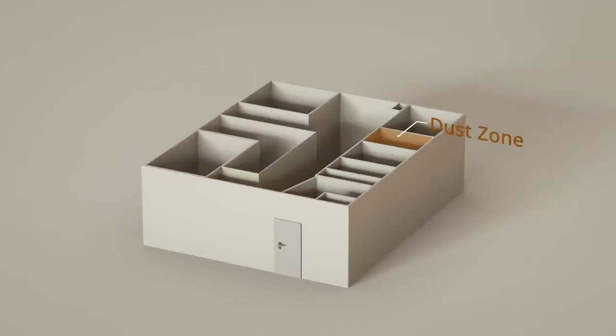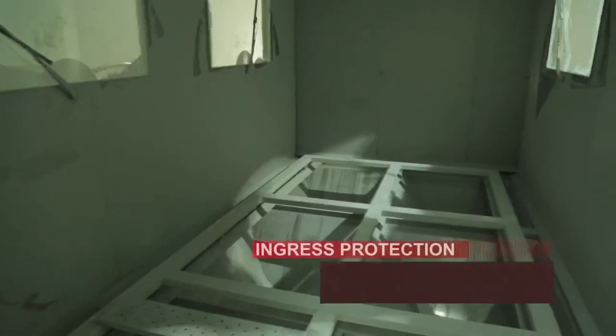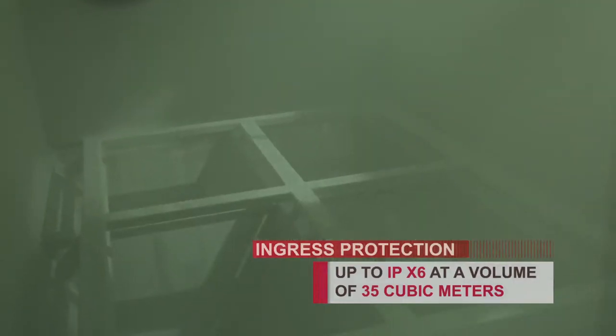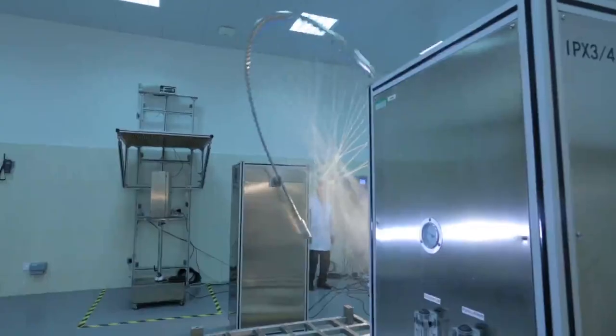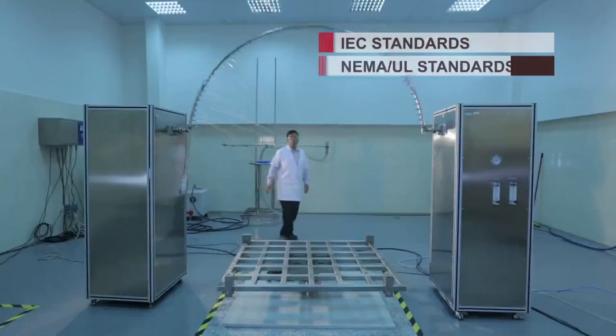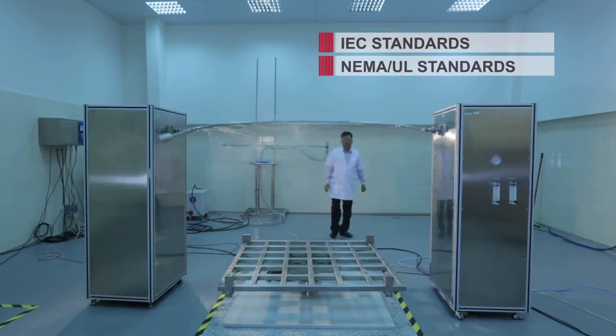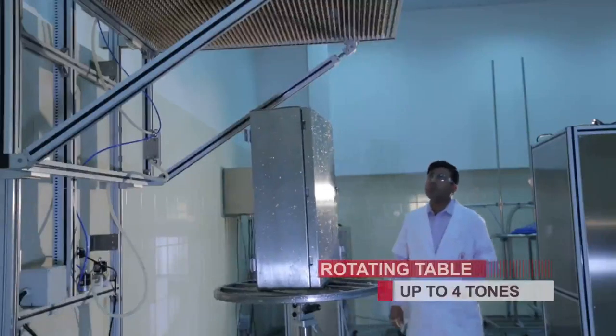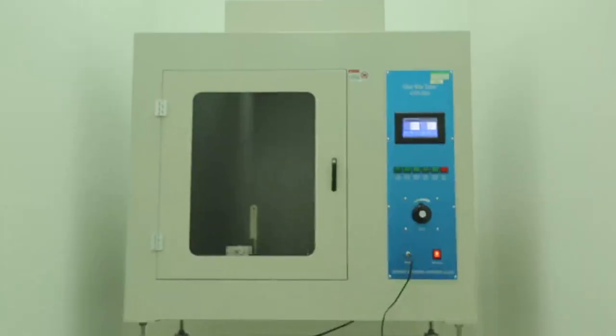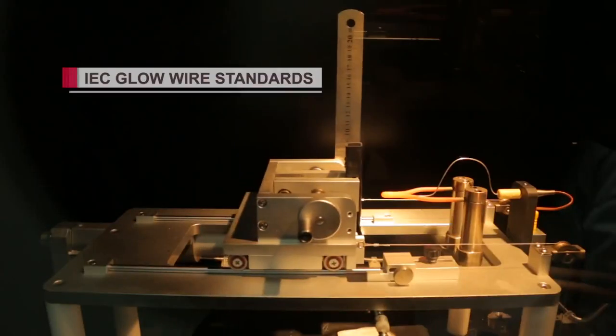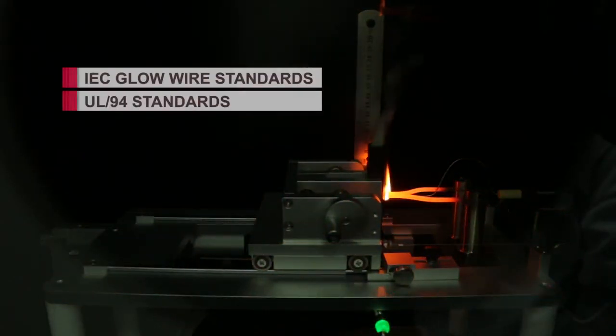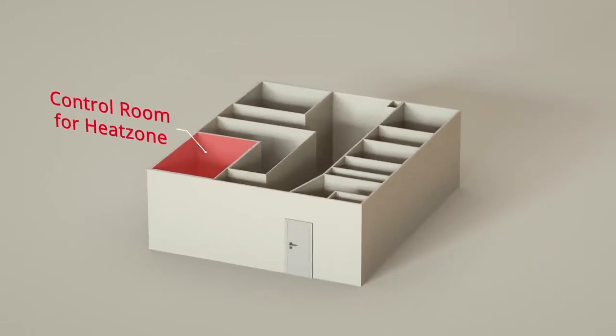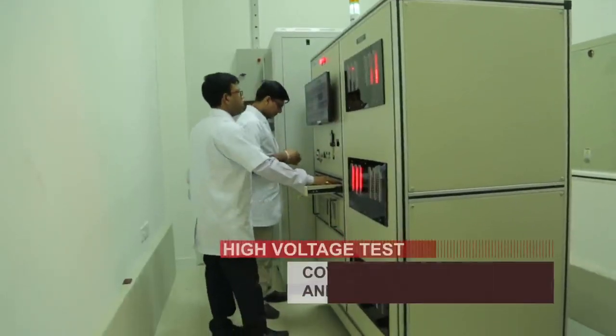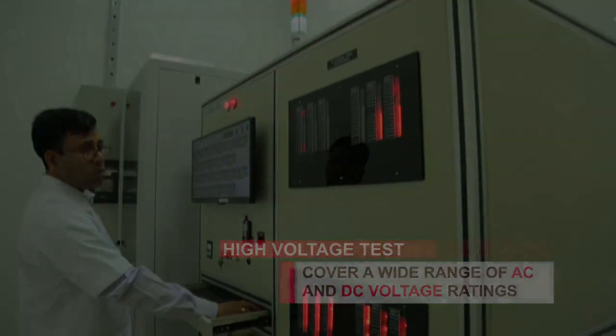The dust zone consists of one of the world's largest chambers for ingress protection, testing up to IP6X at a volume of 35 cubic meters. The aqua zone water test is designed to cater to IP for IEC standards, as well as type ratings for NEMA or UL standards. The rotating table can be inclined and bear a load up to 4 tons. The insulating materials lab zone tests as per the widely accepted IEC glow wire and UL 94 standards. Finally, the high voltage and impulse voltage test capabilities cover a wide range of AC and DC voltage ratings.